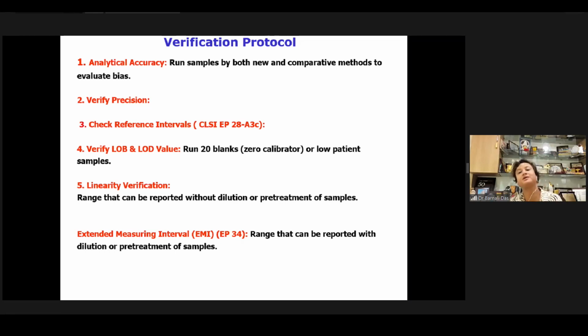Why? Because the instrument manufacturer, the IVD manufacturer, like Mindray, does its validation, and in that they mention that you can dilute the sample up to that range. Beyond that, we are not supposed to dilute. So we can't dilute any sample to infinity. Whatever limits the manufacturer mentions, we can verify, and we should have our CRR or EMI chart displayed in the lab, so that no technical staff, even at night, releases any report which is beyond the extended measuring interval, or CRR.